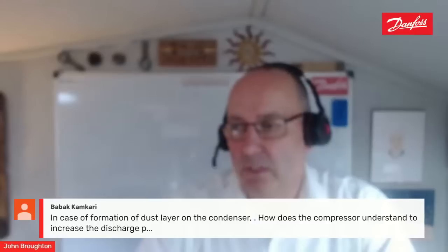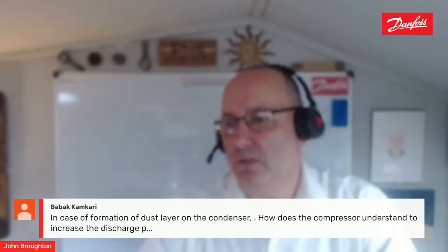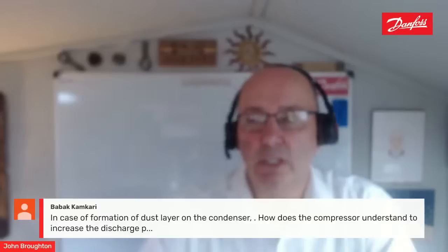So the system will increase the discharge pressure, but more importantly, it will also increase the discharge temperature, and that's what we don't want with a compressor. If we have high discharge temperature, the compressor has to work much harder. We have a bigger temperature lift on that compressor, which puts a lot of strain on the mechanicals. If we get very high discharge temperatures, we then have challenges with the oil and the lubrication qualities of that oil as well. So a clean condenser is incredibly important.